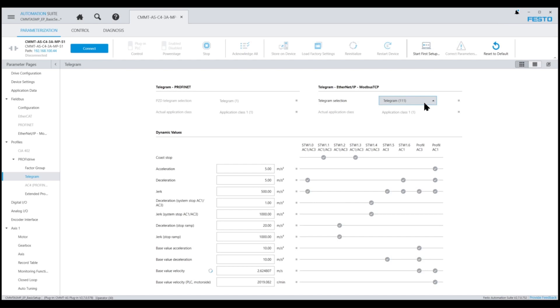In order to locate the acceleration and deceleration parameters for this type move, we need to look at the column labeled Profile AC3. And the parameters that have a checkmark beside them are the parameters used during a point-to-point MDI or direct mode move. Here you can see the base value acceleration and deceleration parameters are set to 10 meters per second squared.